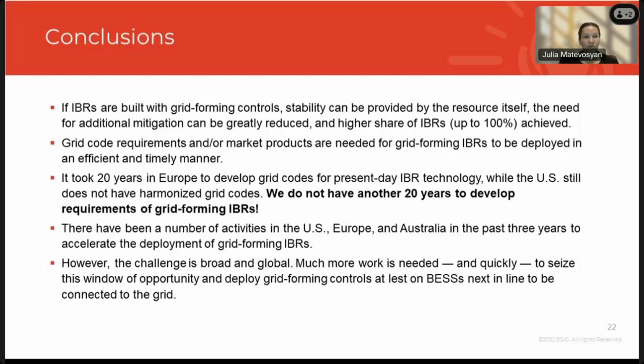The same issue was there with frequency response from solar. And for wind, additionally, it puts mechanical stress on the drive train. So there are more considerations. It's not only that you are backing off and losing revenue, but you also need to take into consideration that there is mechanical stress when providing grid forming capability. That being said, it's been tested in Scotland, and they've shown that it is possible. It's probably that OEMs will need more work and more research to understand how much hit the drive train takes and what it costs, and maybe price it accordingly.